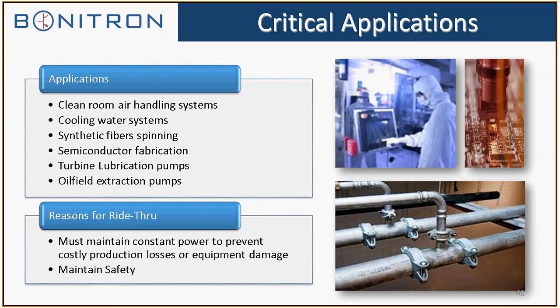Also, a fairly new one over the past few years, oil field extraction pumps, or PCP pumps. This is also an issue of equipment damage. When you have a long line going down into the ground that's pulling up oil, what happens is when the drive that's doing the pumping shuts off, the line that goes down into the oil reserve will backspin and create regenerative energy, which will trip the drive on overvoltage, and it can also damage the pumping line. So there's two solutions for this.